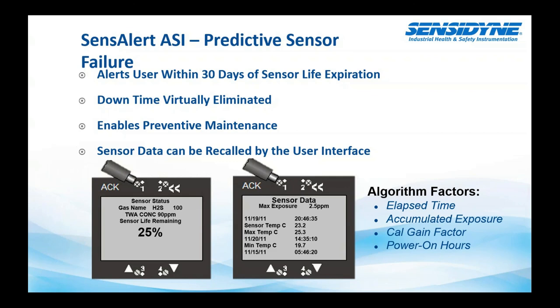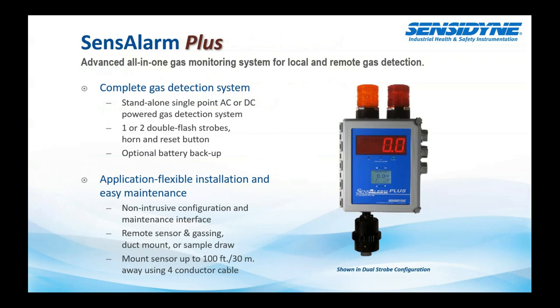It takes that all into consideration and gives you a predictive end of life of the sensor. You can also tie this into a relay output, so you can alert your operators in the control room or in your safety system that this is a sensor that is going to be failing soon, and will enable you to order a new sensor, and that way you have no downtime of your safety systems, which obviously is very important.